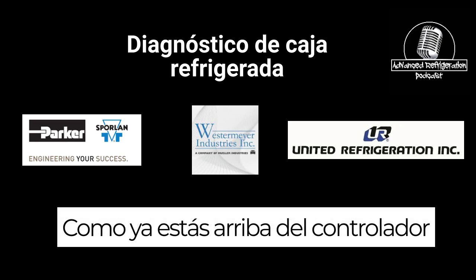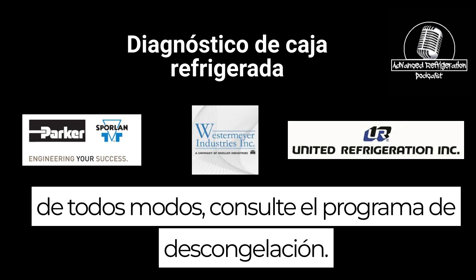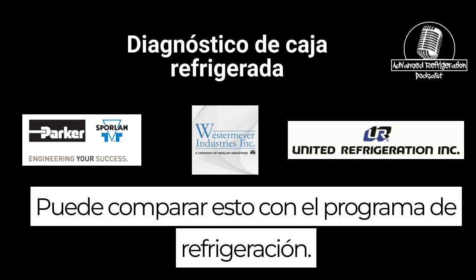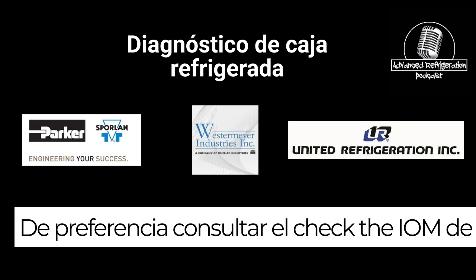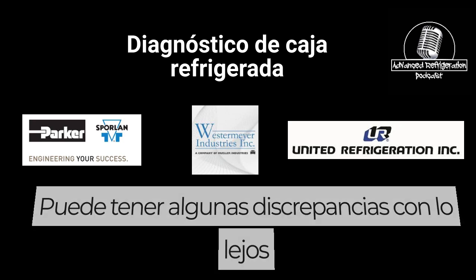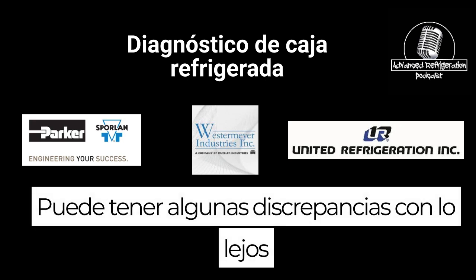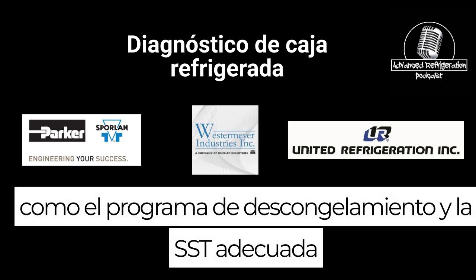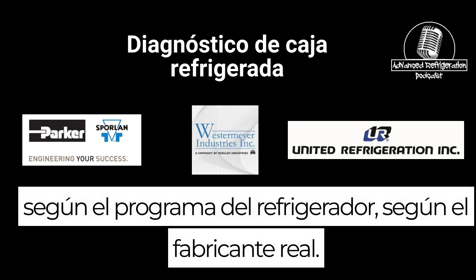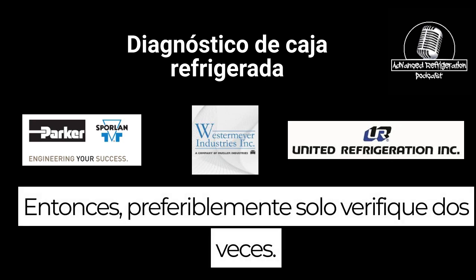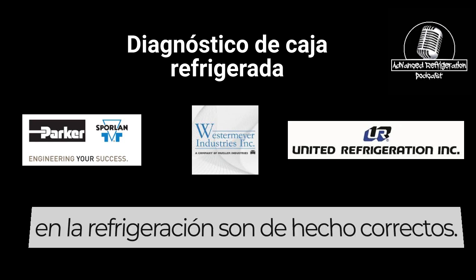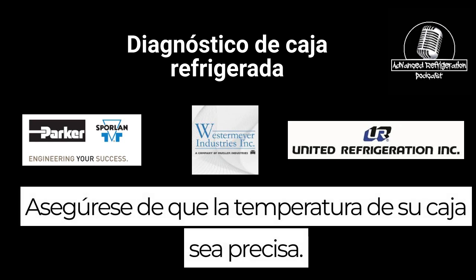Yeah, since you're already up at the controller anyway, check the defrost schedule. You can compare this to the refrigeration schedule. Preferably check the IOM from the internet. I've found in the past you can have some discrepancies as far as the defrost schedule and the proper SST per the refrigeration schedule versus the actual manufacturer. So preferably just double check to make sure all the specs that are actually on the refrigeration schedule are in fact right. Make sure that your case temperature's accurate.